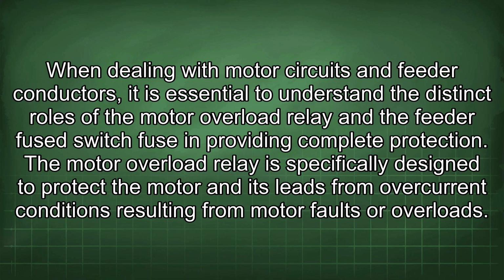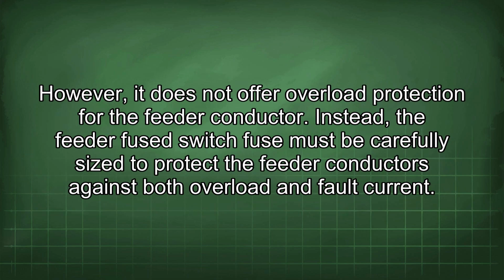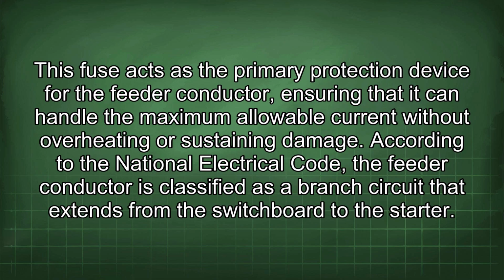The motor overload relay is specifically designed to protect the motor and its leads from overcurrent conditions resulting from motor faults or overloads. However, it does not offer overload protection for the feeder conductor. Instead, the feeder fused switch fuse must be carefully sized to protect the feeder conductors against both overload and fault current. This fuse acts as the primary protection device for the feeder conductor, ensuring that it can handle the maximum allowable current without overheating or sustaining damage.